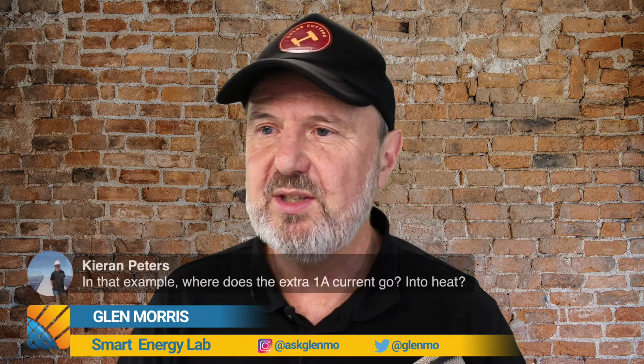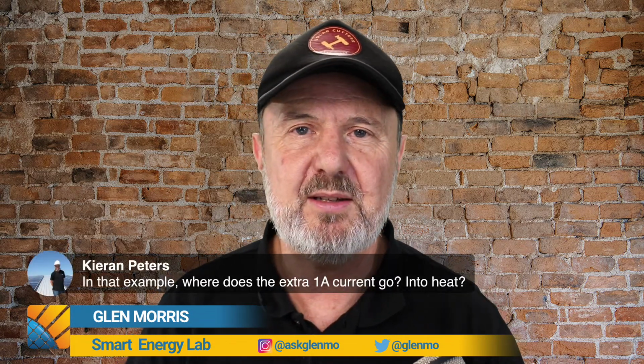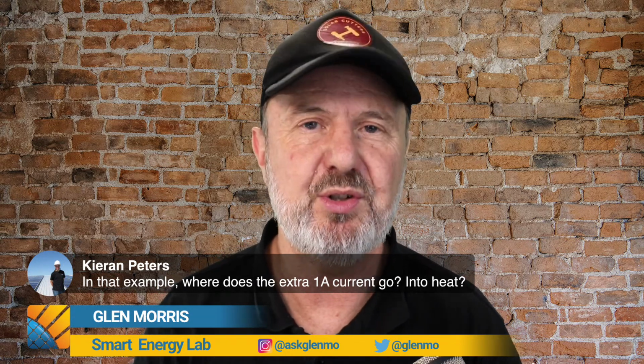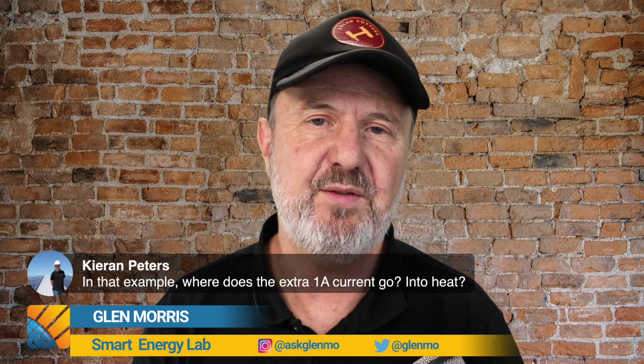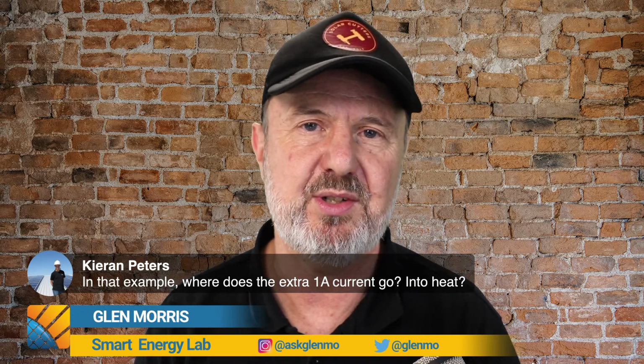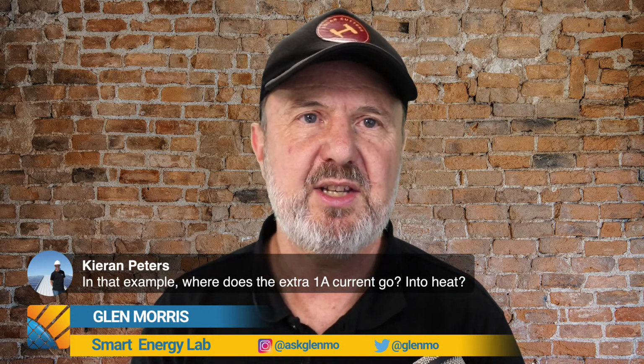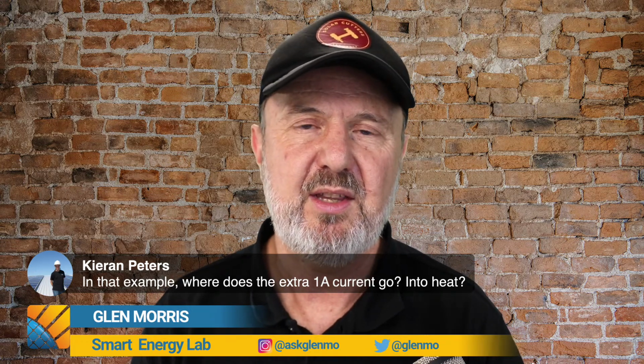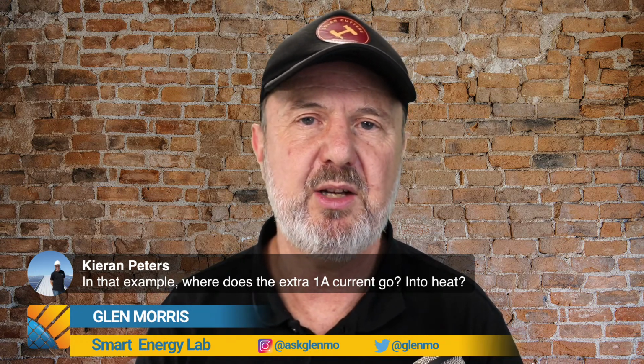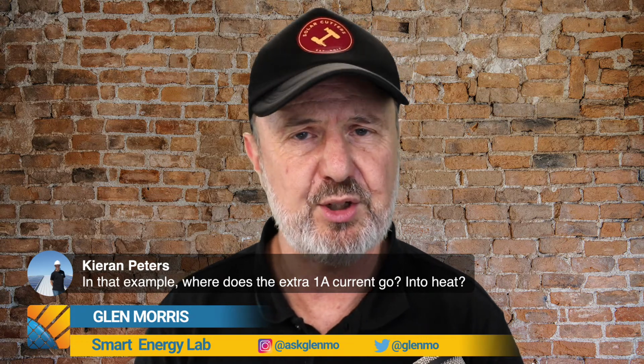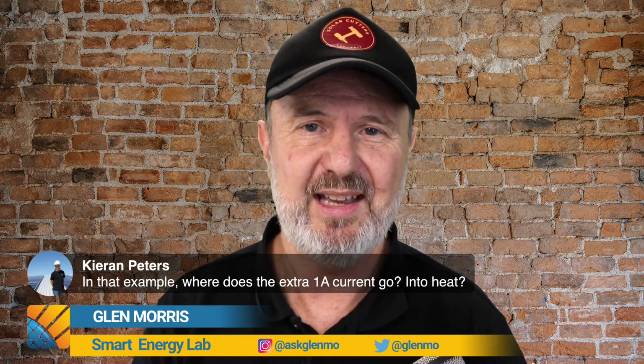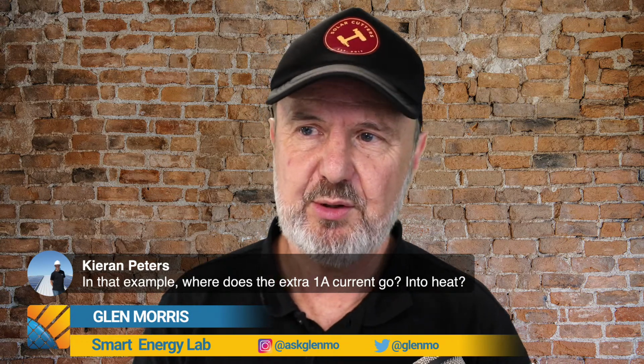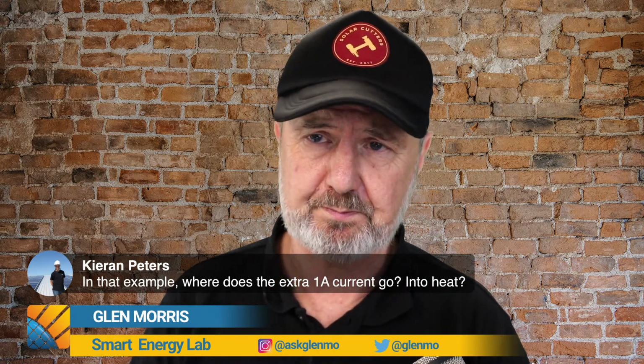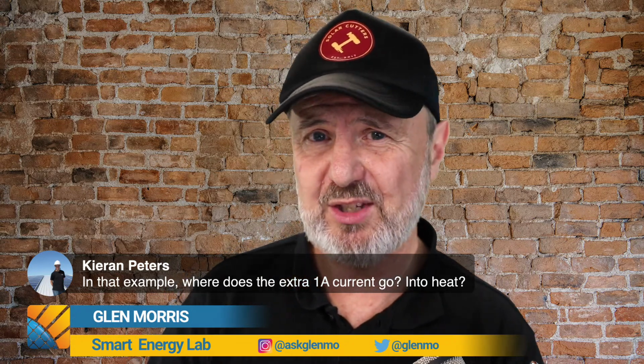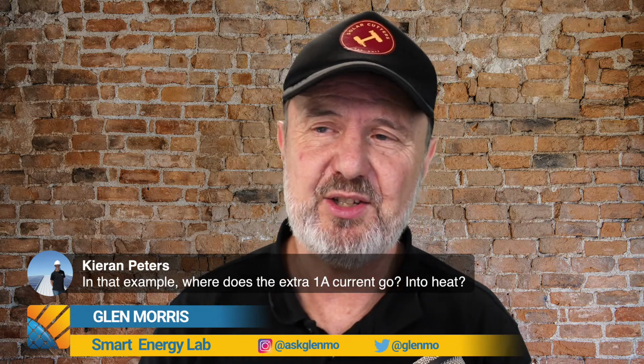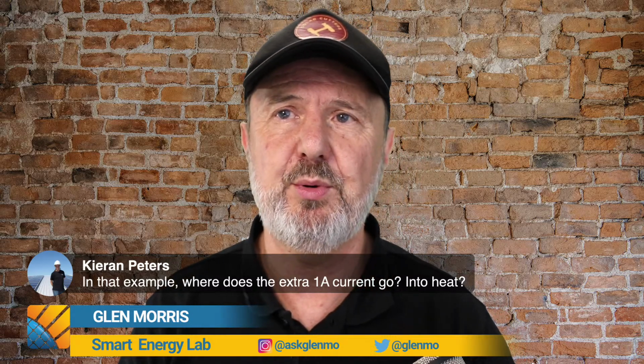I'll just add that question to the screen so you can see it. One of the biggest misconceptions is that the solar panel has to produce power. It doesn't have to produce power. The inverter chooses the amount of power the panels produce. Think of a solar panel as a current source that will deliver up to its maximum depending on what the load requires. An inverter or charge controller can choose how much current to draw from that panel. So in the case of adding that extra panel into the string, the extra amp never gets produced. You're actually operating the panel at an inefficient point on the IV curve.